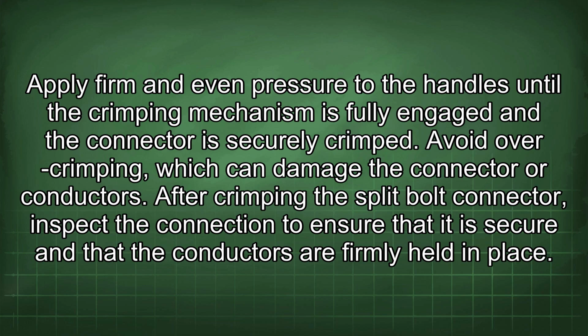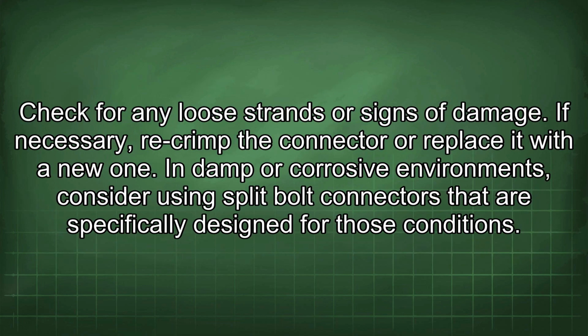After crimping the split bolt connector, inspect the connection to ensure that it is secure and that the conductors are firmly held in place. Check for any loose strands or signs of damage. If necessary, re-crimp the connector or replace it with a new one.